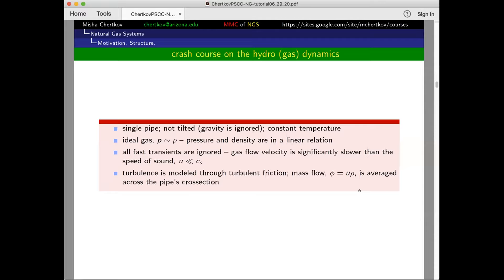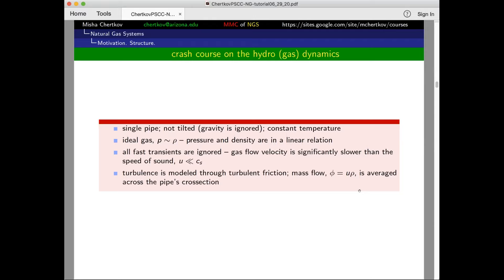Gas is turbulent — when you look at how an individual molecule of gas moves, it moves stochastically within a pipe. But the pipe is much longer than it is wide: you travel hundreds of kilometers and the diameter may be half a meter or a meter. So you basically walk in a one-dimensional approximation. There is also mass flow, which is a significant and important characteristic, along with density and velocity. Everything is formulated in those terms. We are interested in the regime of slow dynamics with respect to fast transients, and all those fast transients are damped through the friction I mentioned. So we will not go into sub-seconds — we are probably living in minutes to hours.